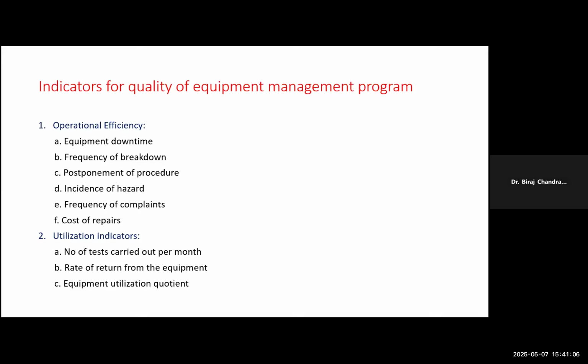In this, we will be checking the downtime. How much was the downtime of the equipment? Then the frequency of breakdown. We can get the efficiency of the equipment from the number of times it broke down. Then postponement of procedures: how many times was a procedure postponed due to non-functioning of the equipment? Incidents of hazard to the patient or to the staff. Then frequency of complaints from the end user. Then cost of repairs, whether the cost of repair is escalating every time.